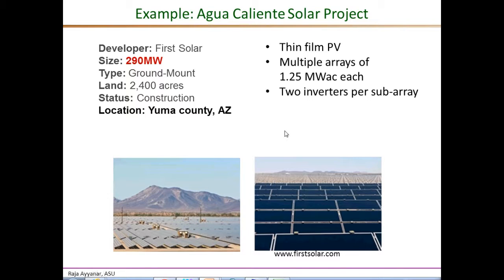This is an example of a large utility scale PV power plant in Yuma County, Arizona, not too far from ASU. This is the Agua Caliente solar project, spread over 2,400 acres. When completed, it will generate a peak power of 290 megawatts. The panels are arranged in multiple sub-arrays of 1.25 megawatts AC each, and each sub-array is supported by two central inverters, which you can clearly see in the image.